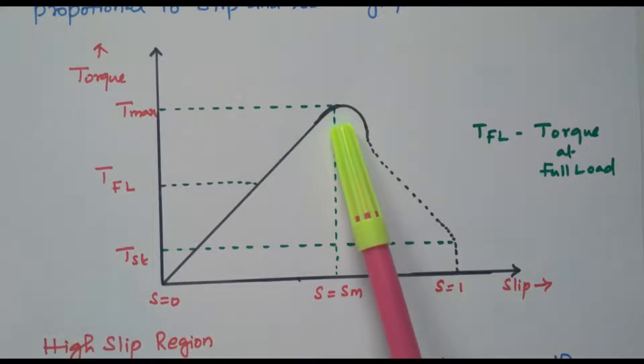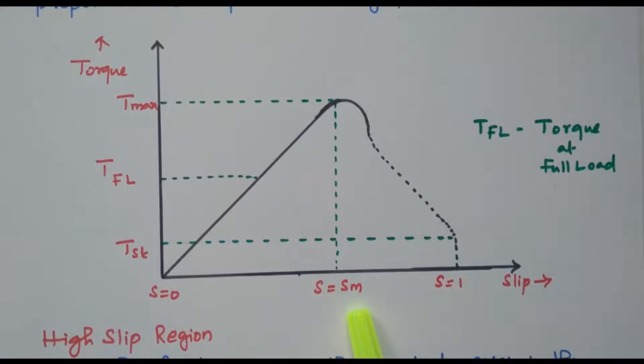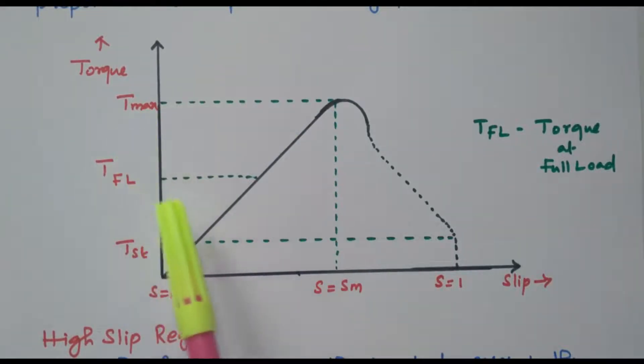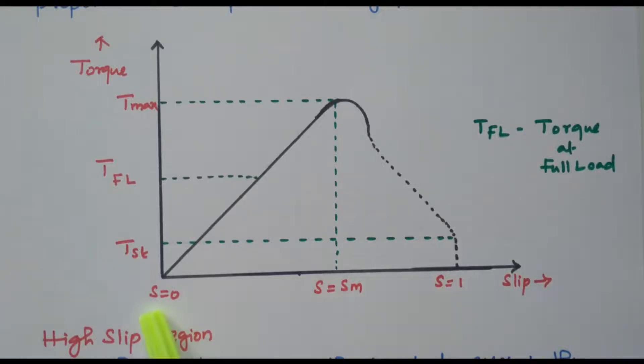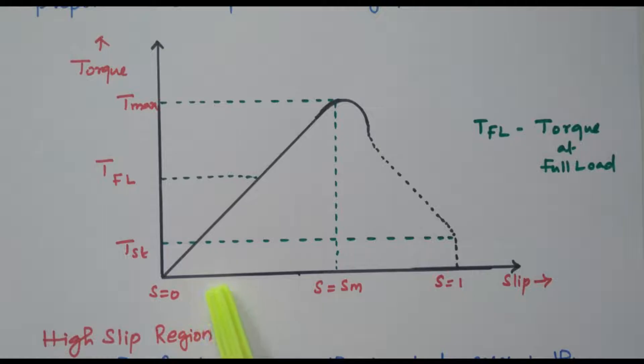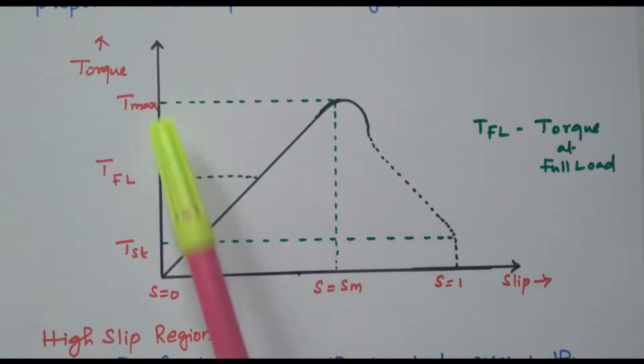At the maximum point, S equals S_M — the slip corresponding to maximum torque. This is the maximum torque, T_max. Approximately half of this is the full load torque, T_FL. So S equal to 0 means torque and slip are both 0, and the curve starts at 0. During the low slip region, slip increases and torque also increases, giving a straight line up to the maximum point — maximum torque at the corresponding slip value.